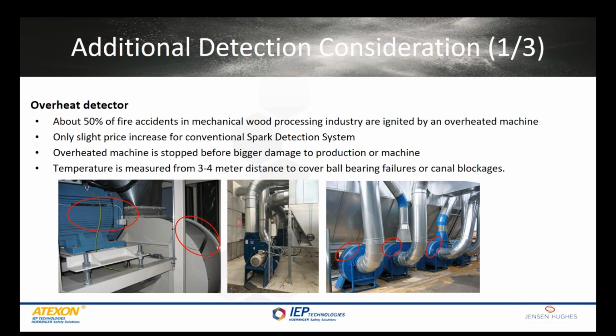Overheat detection is an economic solution if the spark detection system supports this function as a standard, and no external units are needed. It can increase the safety level significantly and also provide preventative maintenance, because ball bearing failure is detected when the temperature is only 100 degrees Celsius, thus not being able to cause bigger damage to the machine before the machine is stopped.